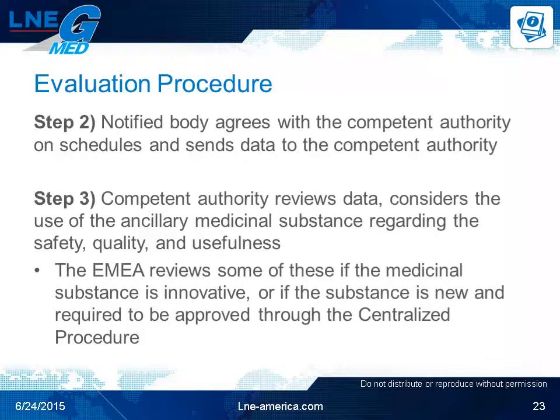The second step, notified body agrees with the competent authority on schedules and sends data to the competent authority. The third step, competent authority reviews data, considers the use of ancillary medicinal substances regarding the safety, quality, and usefulness. The EMEA reviews some of these if the medicinal substance is innovative or if the substance is new and required to be approved through the centralized procedure. Please check with your competent authority on any special documentation requirements they may have, including time frames, since all competent authorities are a bit different from each other.